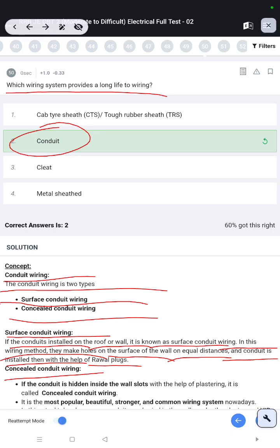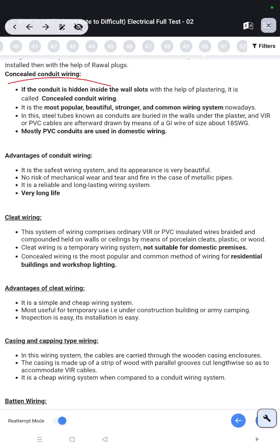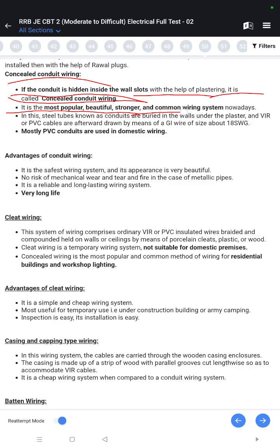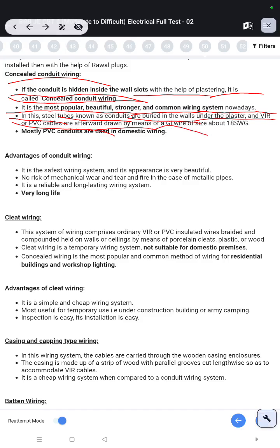Concealed conduit wiring. If the conduit is hidden inside the wall slots with the help of plastering, it is called concealed conduit wiring. It is the most popular, beautiful, stronger and common wiring system. Nowadays steel tubes known as conduit are buried in walls under the plaster, and VIR or PVC cable are afterward drawn by means of GI wire of size about 18 SWG. Mostly PVC conduit are used in domestic wiring.